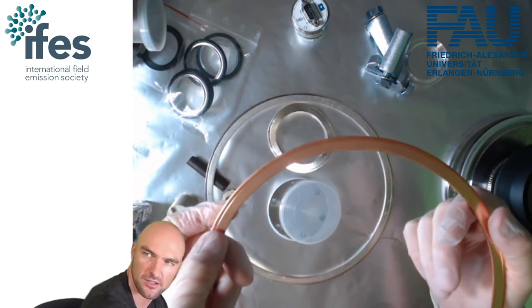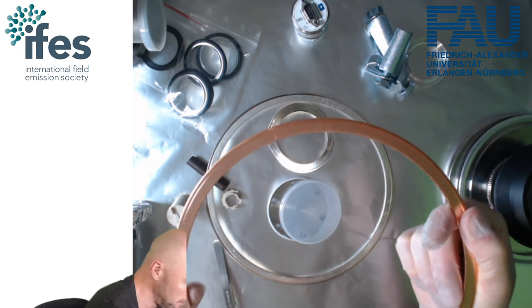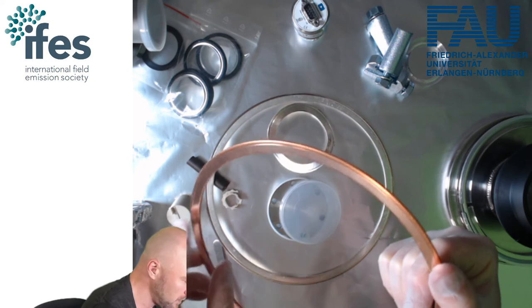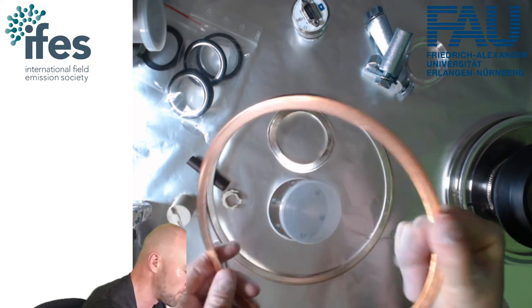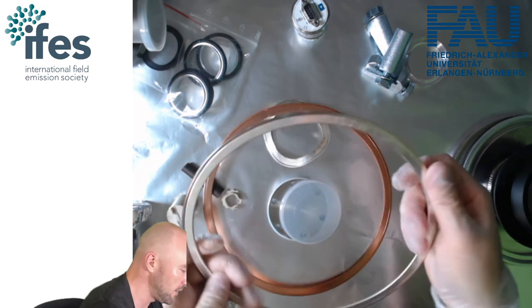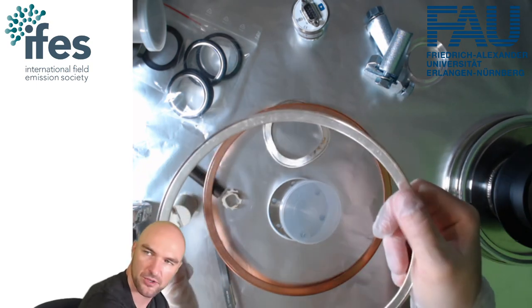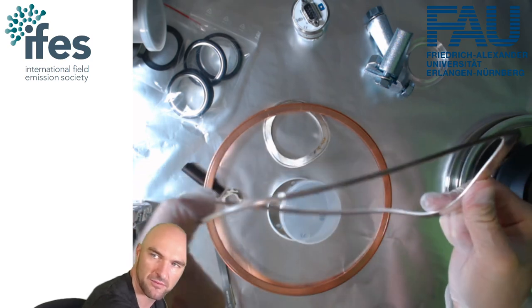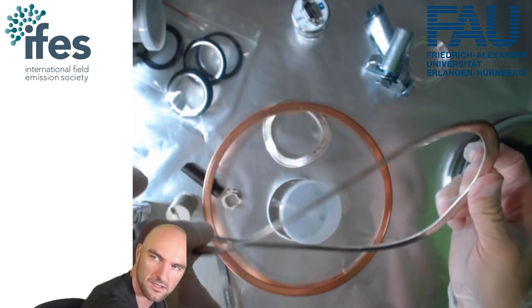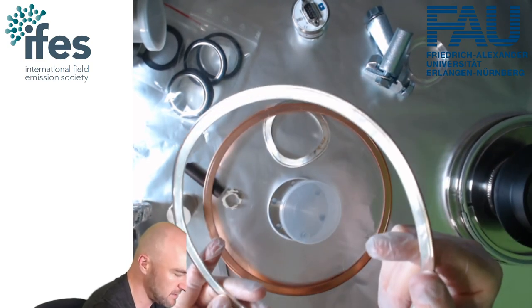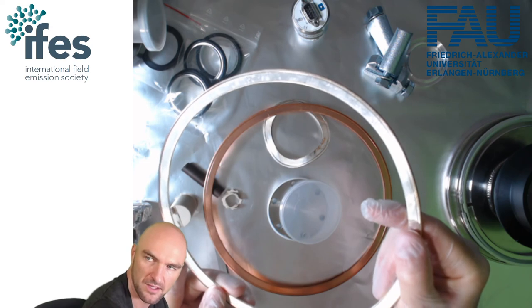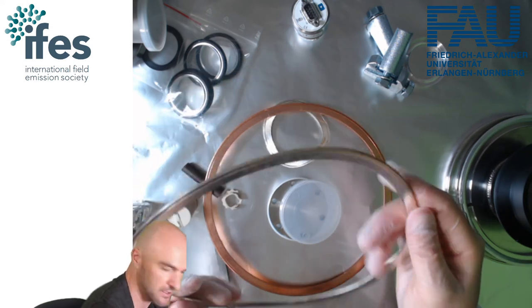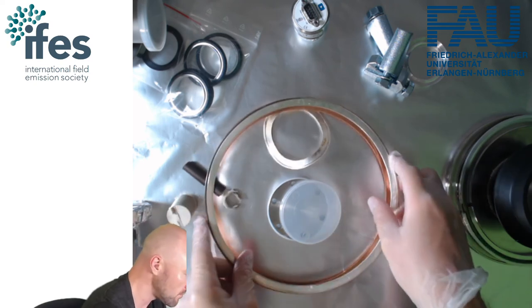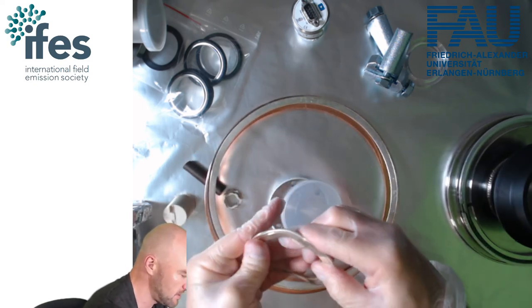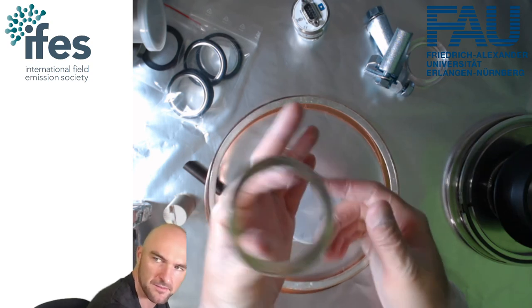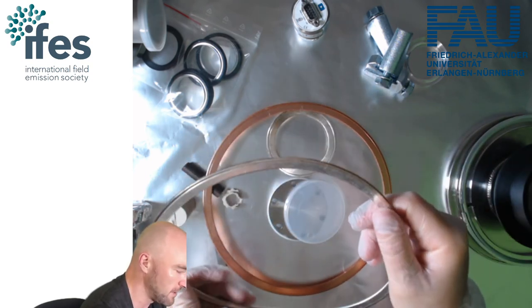And you can see here, this is a used one, so you can see where the knife edge had been pushed in. And if you take the seal out, it should have a very nice imprint of the knife edge all around it. Then here, what we have is a silver plated version, and you can see I can very easily, even just with my fingers, bend the whole seal. And the reason is that this seal has been both copper, both silver plated, and is also annealed, so it's much, much softer. Now, this here is the same thing, just in a different size. So this is for 63 millimeter inner diameter. Yeah? And this is for 200 millimeter inner diameter.